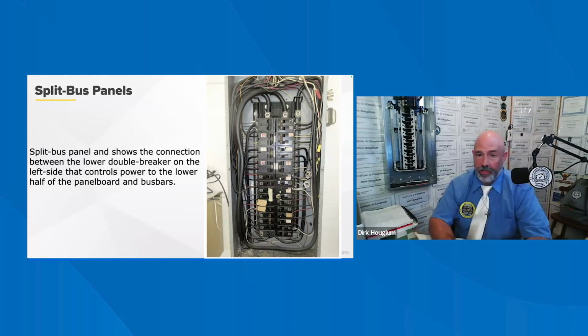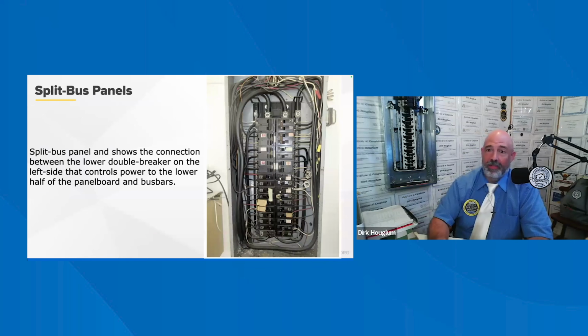Split bus panels, between the 1950s and 1980s, do not have a main breaker or main disconnect. They have two bus sections, typically the upper bus with the double pole 240-volt breakers, including one that feeds the lower bus section where the majority of the 120 breakers are installed. Normally, these panels will have multiple color double pole breakers at the top of the panel, controlling the usual 240-volt circuits, such as for clothes dryers, stoves, air conditioners, and so on.